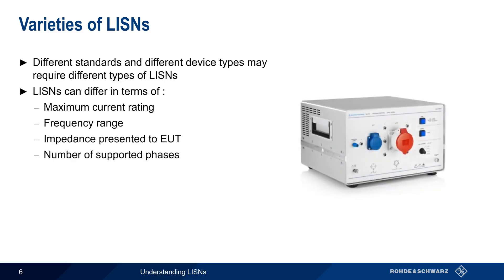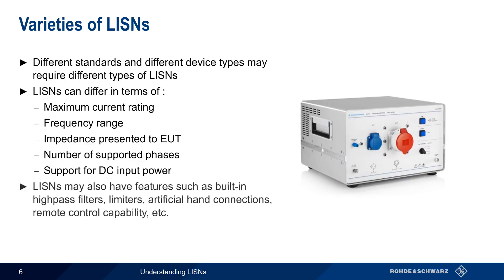Different types of LISNs may be required depending on the test standard and the equipment under test. For example, LISNs may differ in terms of their maximum current rating, frequency range, and the impedance they present to the EUT. Some LISNs support different numbers of phases, such as the one shown here, or may support DC input power. In addition to differences in basic specifications, some LISNs have additional features such as high-pass filters, limiters, remote control capability, etc.